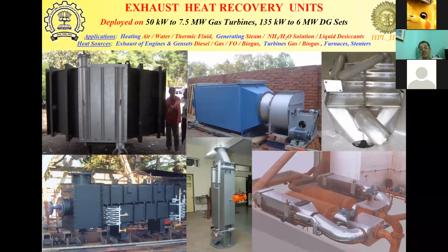And then the steam was used for operating absorption refrigeration systems, a lithium bromide 2-stage double effect lithium bromide water system, to produce chilled water for the hotel. So this is an example where you can recover heat from gensets and use the exhaust for producing additional cooling. So you're talking about cogeneration.